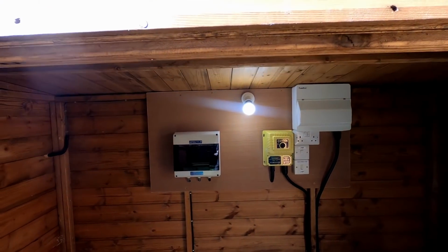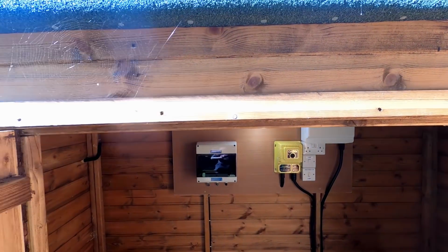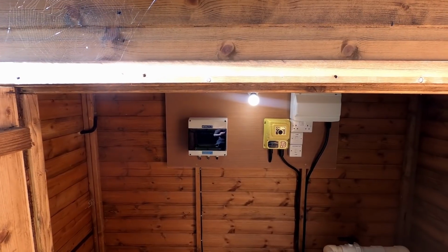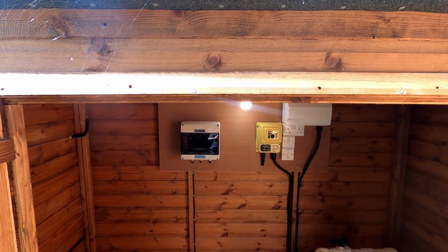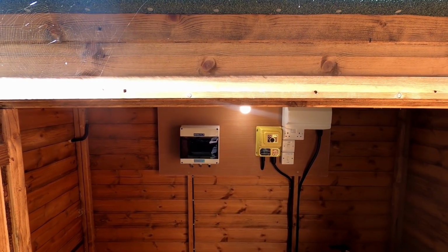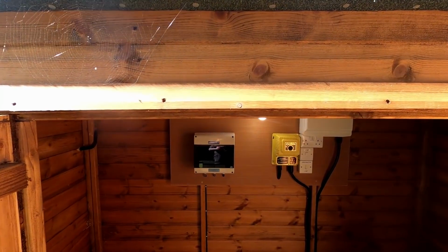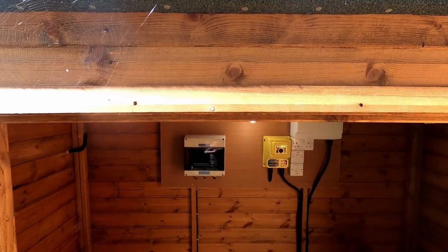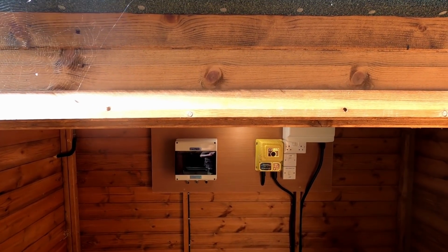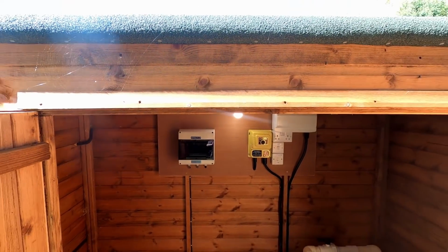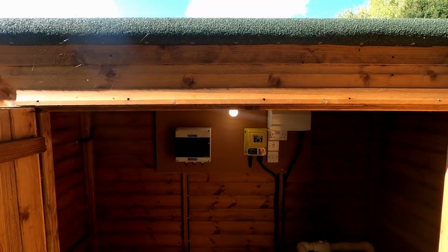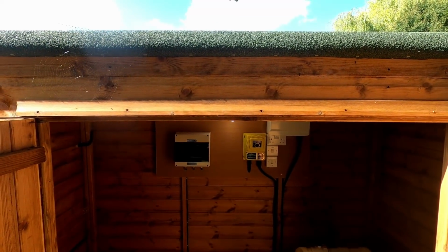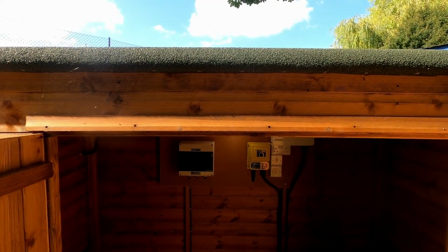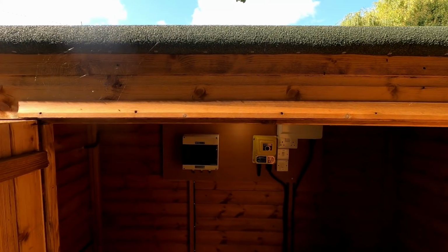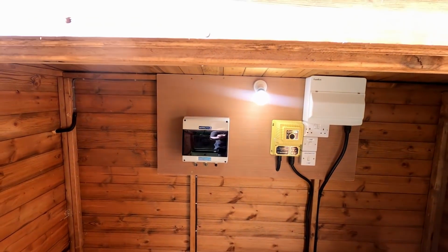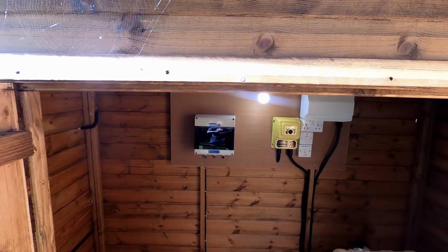That control unit controls both the pump and the heat exchanger, but the instructions are very vague when it comes to what goes where. It doesn't even tell you where your line and neutral is for the pump. It just says connecting to these 2 pins, so I had to actually trace that out. But obviously the fuse rating is for the pump, so where do I connect my 16 amp connection for the heat exchanger? And it's not on that breaker, before anybody obviously comments. It's meant to go off one of the contactors or something, maybe even the timer. I'm not entirely sure, so I'm just waiting on that call back.